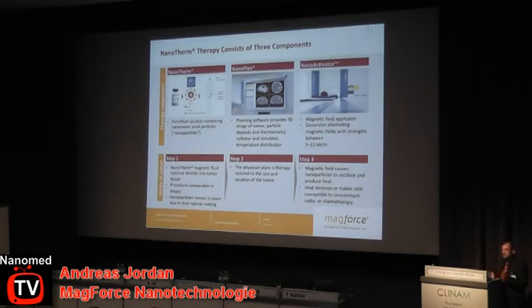So it's the first system which is able to deliver hyperthermia, which is a low temperature range, to increase the effect of chemotherapy or radiation therapy. But with the same system, by increasing the magnetic field strength and the magnetic particle concentration in the target region, you can also get temperatures which are clearly thermoablation, meaning temperatures of 50, 60, or 70 degrees centigrade, which are almost only possible with thermoablation systems, quite different devices available on the market. So if you are a physician doing thermotherapy, hyperthermia, or thermoablation in the clinic, you would have to have different systems, but this is an all-in-one solution where you can do both.